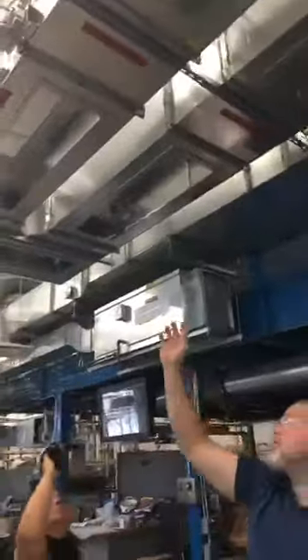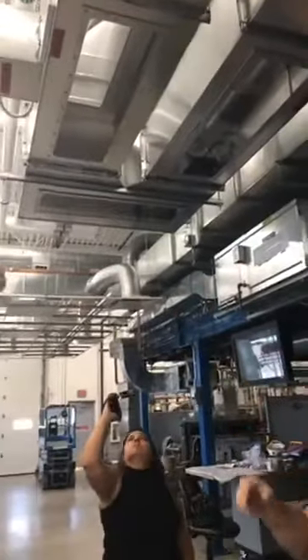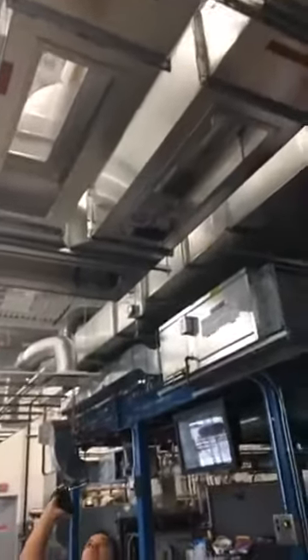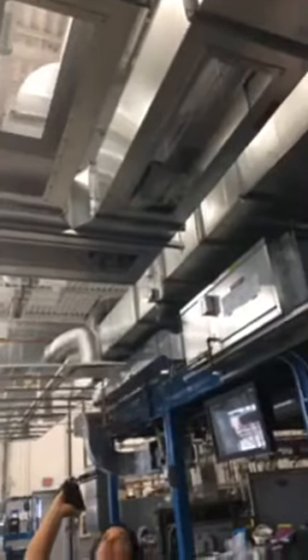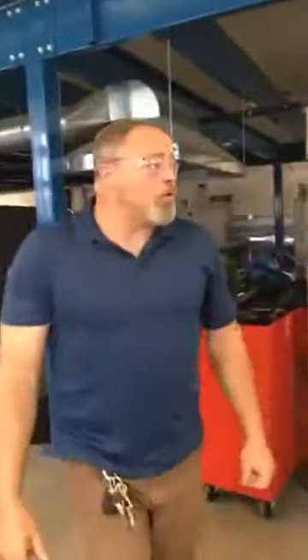And we'll also demonstrate a plume of smoke coming out in a failed system or a simulated failed system. Then the smoke would travel through, and we have an exhaust fan on the roof that would ventilate the system so we don't choke ourselves out here. So we'll start with a demonstration on the smoke introduced through the duct system with all the dampers open and our lead damper closed to just show how smoke travels through ductwork and how quickly it actually moves through the ductwork.